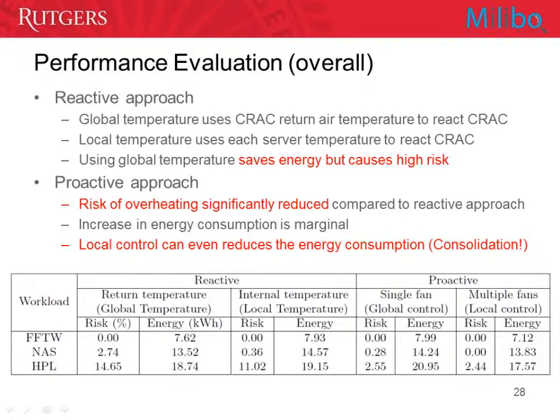If you use return air temperature for feedback, that's the mixed air for all the servers. In the second case, if any server in your data center exceeds a recommended temperature, you react. This graph shows that risk decreases from return air temperature to internal temperature feedback, because you're more conservative in reacting—but you consume more energy to cool down your servers as a result.